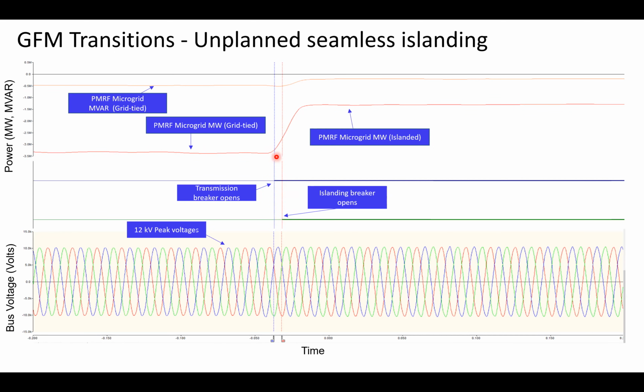Once the islanding breaker opened, the AES plant had to drop its power output down to match the PMRF naval loads, which were at about 1.1 to 1.5 megawatts. So that's essentially a seamless islanding with no interruption in power to the PMRF loads. In reality, since this was a test, it was kind of manual. We try to make it an unexpected test, but really we are dictating the test by choosing the dispatch, choosing when the breaker opens. It's probably the only way to really test it.